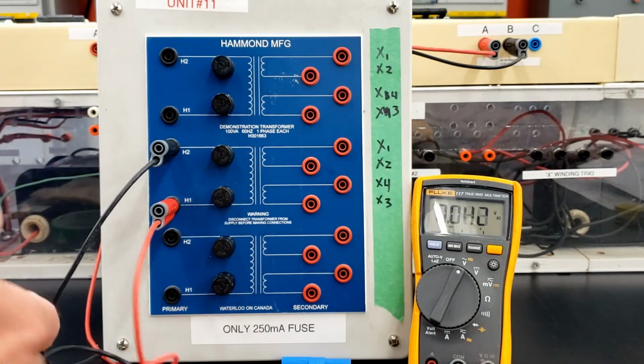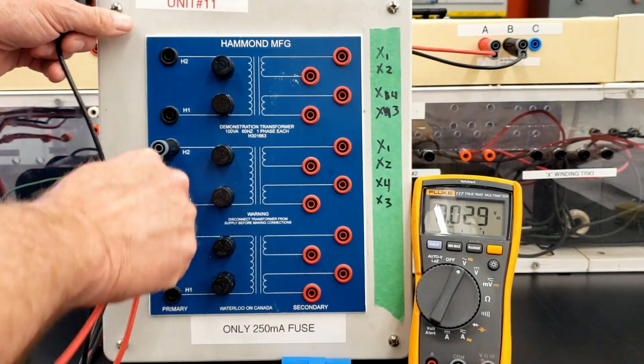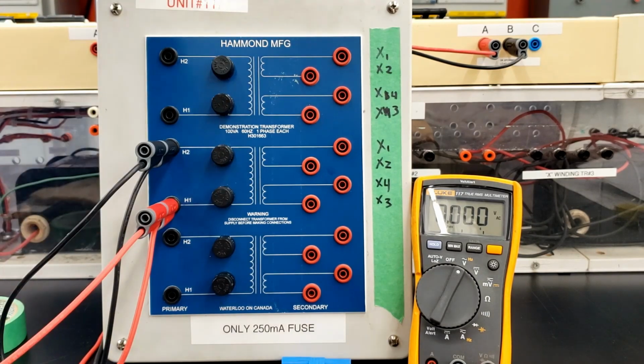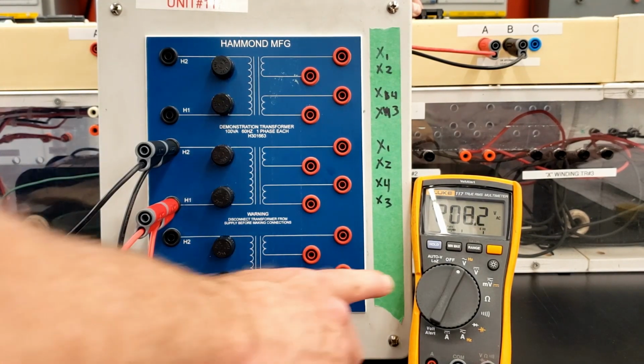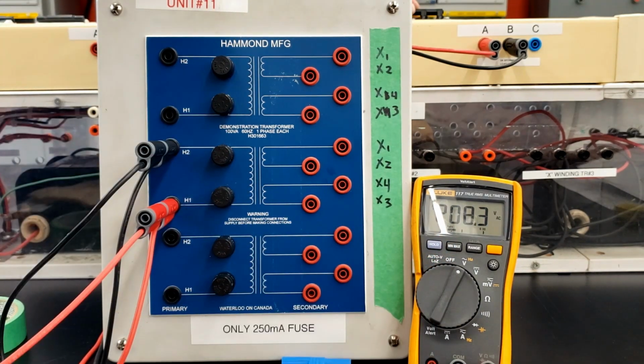Okay, next thing we're going to do is we'll check out the voltage. So again, we'll see here on our primary, we'll have 208. Now again, this voltage changes day to day depending on what loads are on the rest of the floor. There's a big compressor that turns on. Sometimes the voltage goes down to 207, sometimes down to 206, sometimes it's 209, but today it's a gorgeous 208.